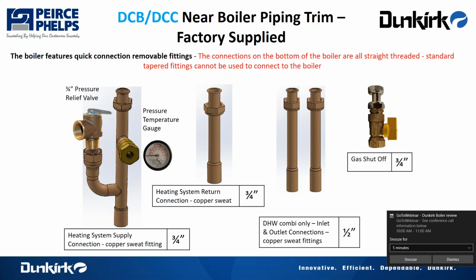The system return piping also goes into the bottom of the boiler. On the Combi, we also provide the 2 domestic hot water connections. Those are all sweat connections at the bottom that you'll utilize. We also provide a gas shutoff with a 3/4 thread on the bottom. So again, don't go with your own fittings on the bottom of the boiler. Utilize the near boiler piping components that we provide with the boiler.